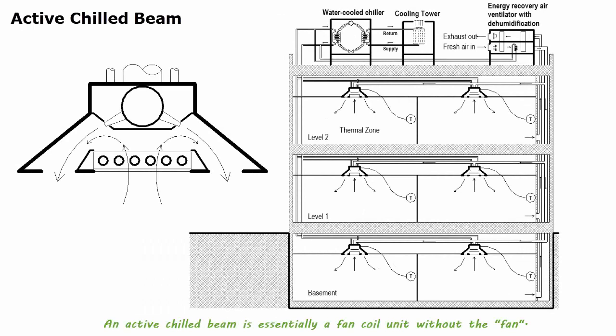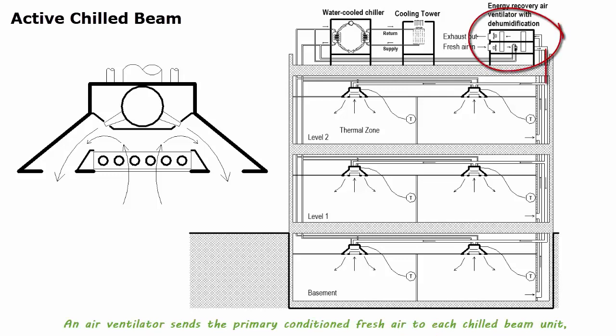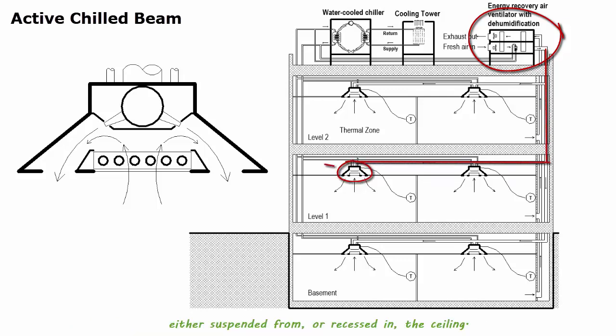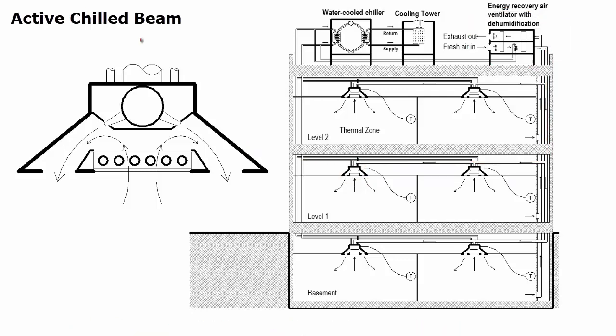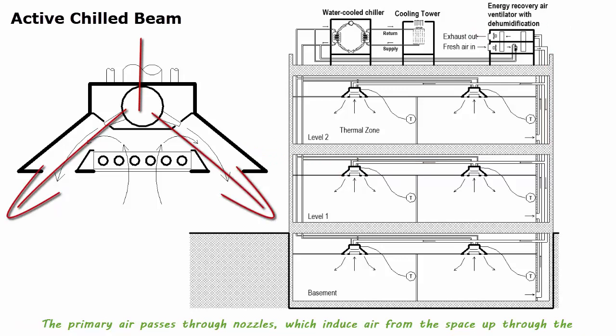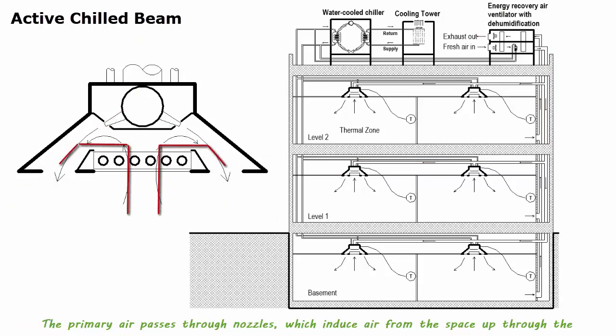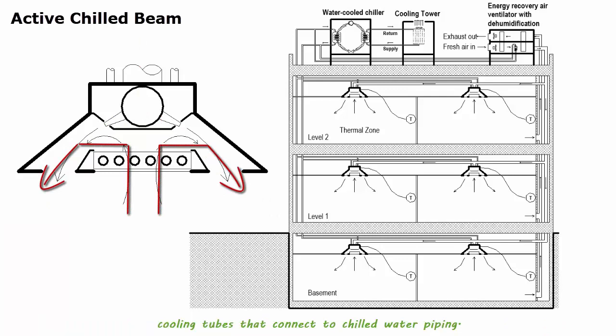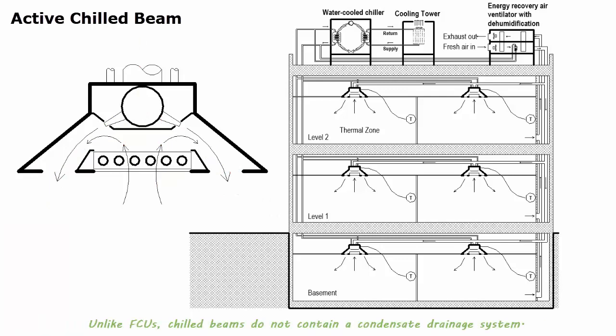An active chill beam is essentially a fan coil unit without the fan. An air ventilator sends the primary conditioned fresh air to each chill beam unit, either suspended from or recessed in the ceiling. The primary air passes through nozzles, which induce air from the space up through the cooling tubes that connect to the chill water piping. Unlike fan coil units, chill beams do not contain a condensation drainage system.